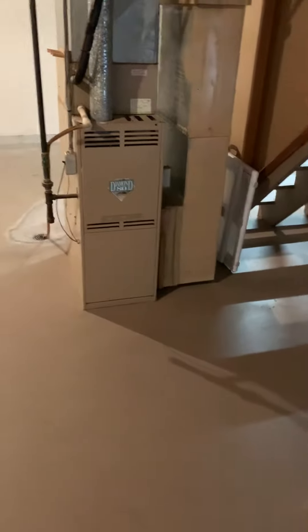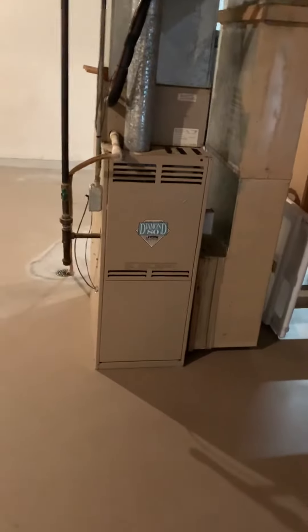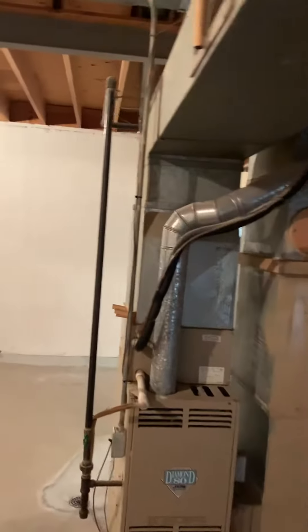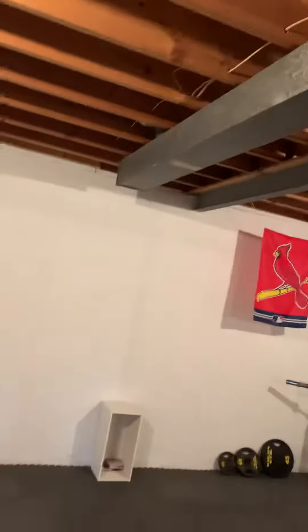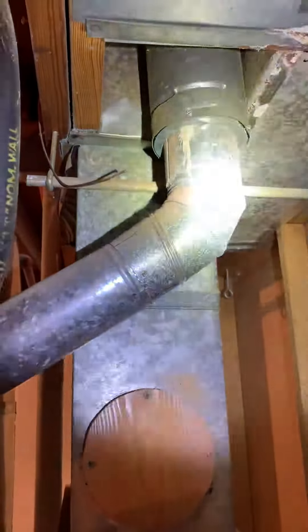Take a look at this furnace replacement — 80,000 BTU — replacing the AC coil and supply plenum. We'll get measurements from here to the supply section. The supply is coming up, running over toward the kitchen, and then running the length of about half the basement. Some runs come off of here. We'll also look at a new return drop for better airflow.